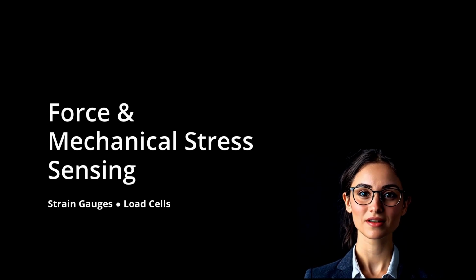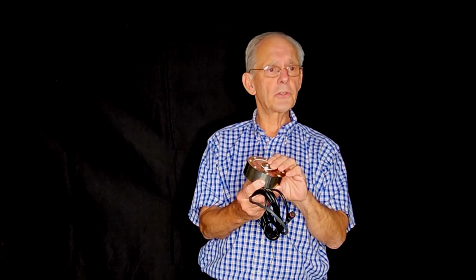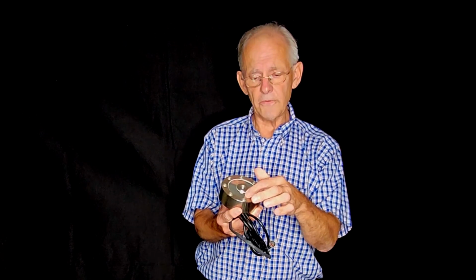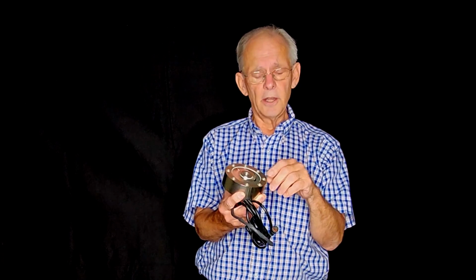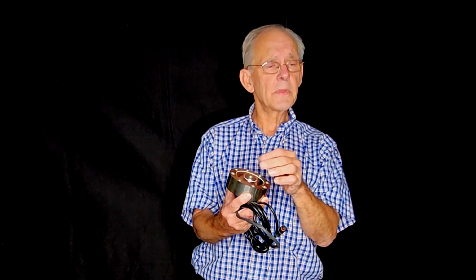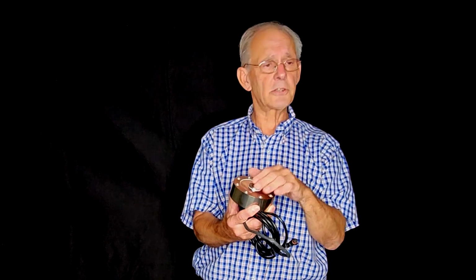Force and mechanical stress sensing. So this is what they call a load cell. This one happens to have a rating of 5,000 kilograms that it can measure, 11,000 pounds. And this uses what's called strain gauges. Inside this cover, this centerpiece moves, and there are fine resistors that, when they get stretched as this bends the beam, the resistance changes. And there's a set of resistors in here that cause an imbalance, and that changes the output voltage. You put a voltage in and you get a voltage out, which varies based on how much weight is on it.